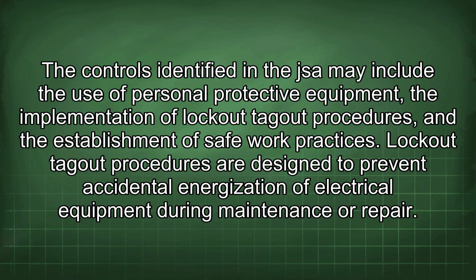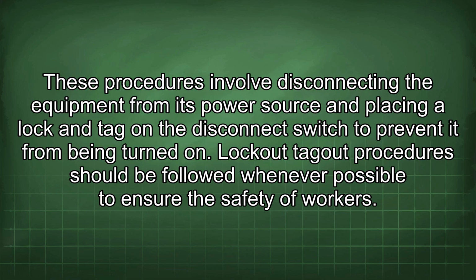Lockout-tagout procedures are designed to prevent accidental energization of electrical equipment during maintenance or repair. These procedures involve disconnecting the equipment from its power source and placing a lock and tag on the disconnect switch to prevent it from being turned on. Lockout-tagout procedures should be followed whenever possible to ensure the safety of workers.